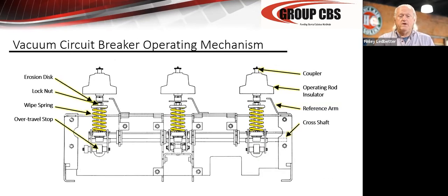Here's, for instance, what we're talking about. If you look right here, you can see the wear indicator. So when this particular disc reaches here, the interrupter needs to be replaced. This is the wipe spring below it, the spring that's in yellow. I guess that's yellow, I'm pretty colorblind. Basically, that wipe spring can continue to do its job up to about 3,000 operations. After that, I would have those wipe springs checked.